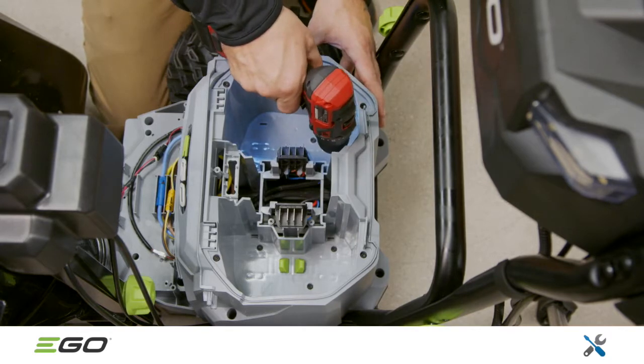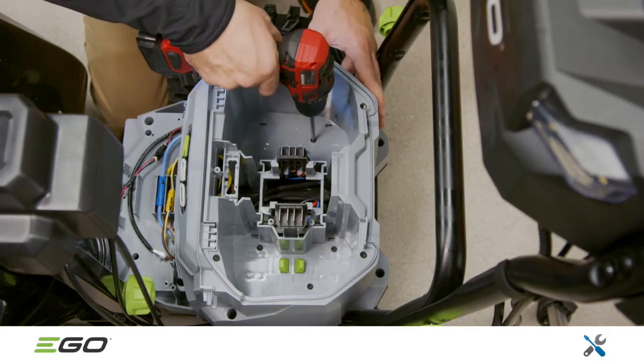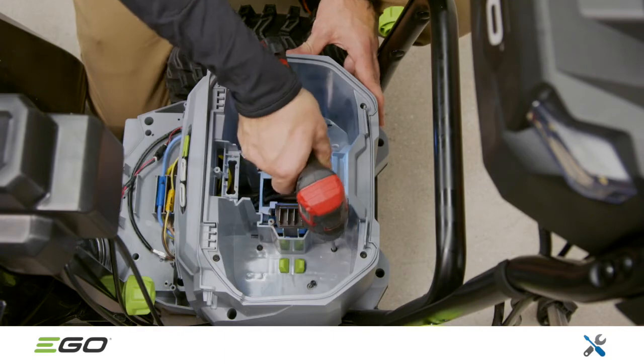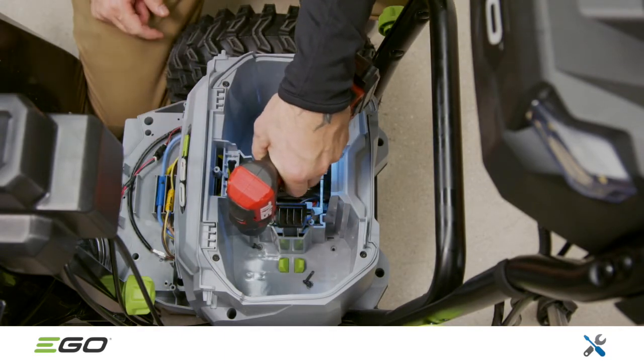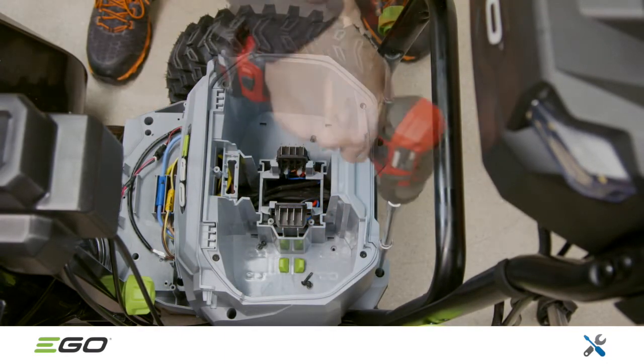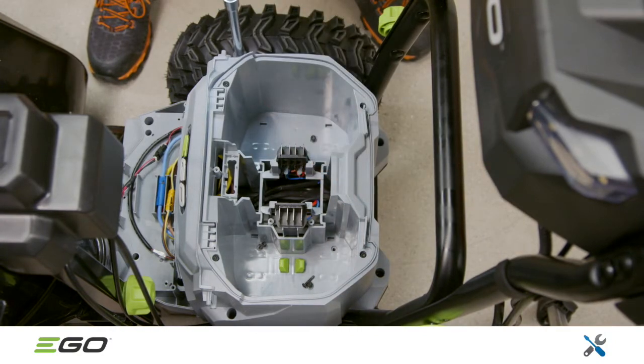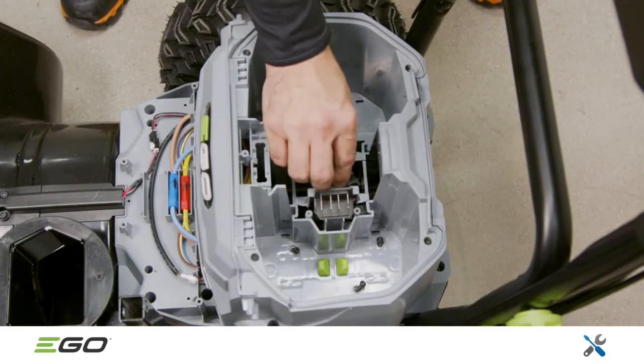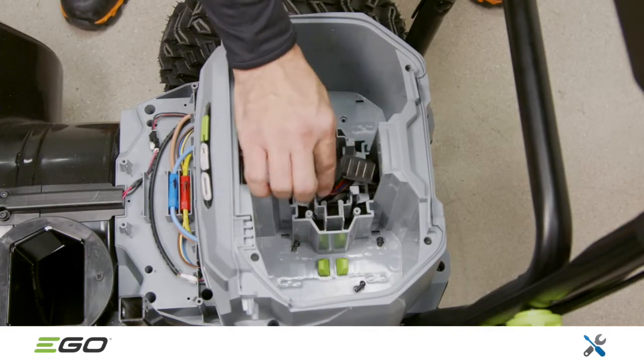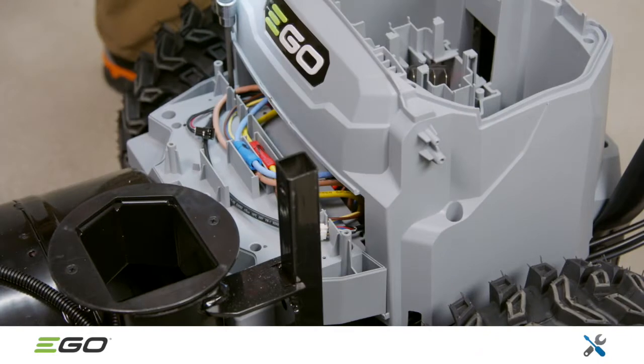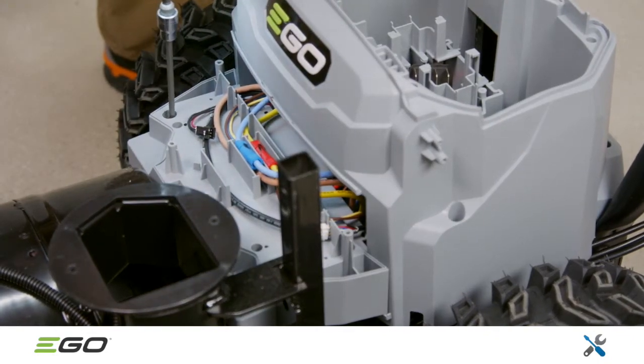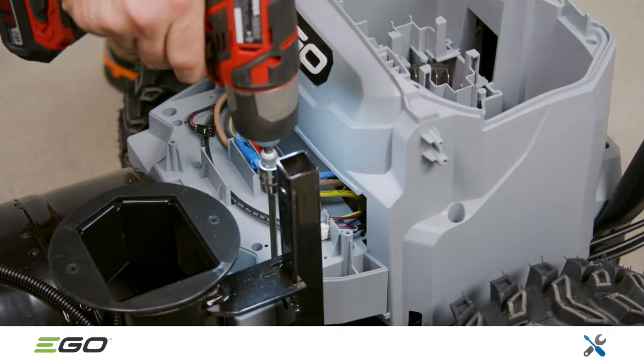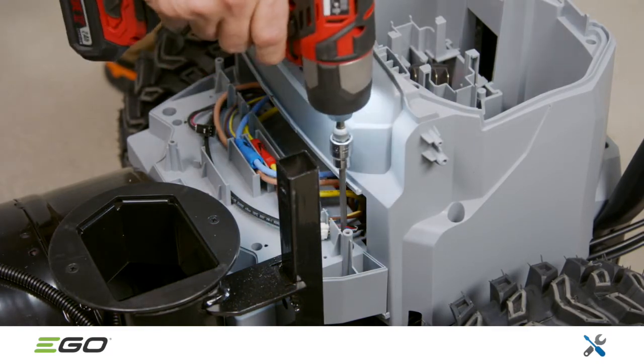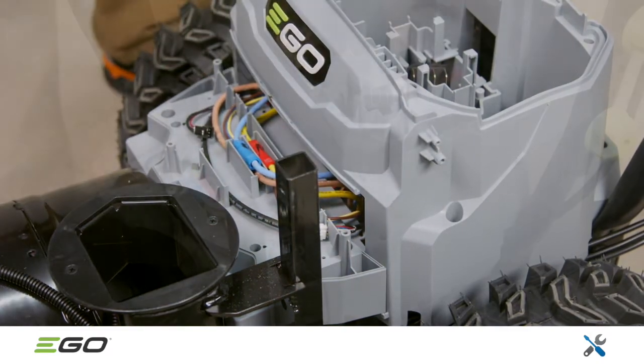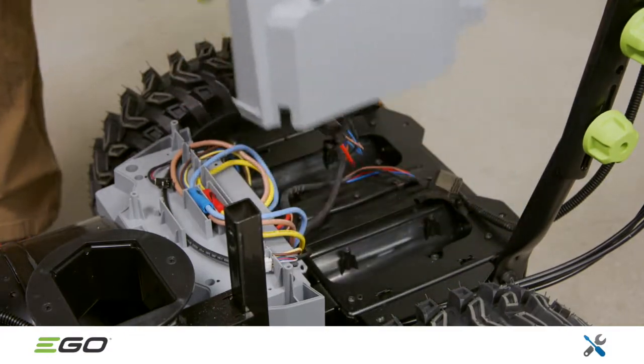Continue by removing the 6 T20 Torx screws inside the battery box, 3 on each side. Then remove the 4 5mm hex screws on the outside of the battery box, 2 on each side. Once all of the battery box screws have been removed, release the 2 power terminals as shown here. Then loosen the 4 5mm hex screws that secure the PCBA assembly. This will allow for removal of the battery box, which is secured with locking tabs on each side.